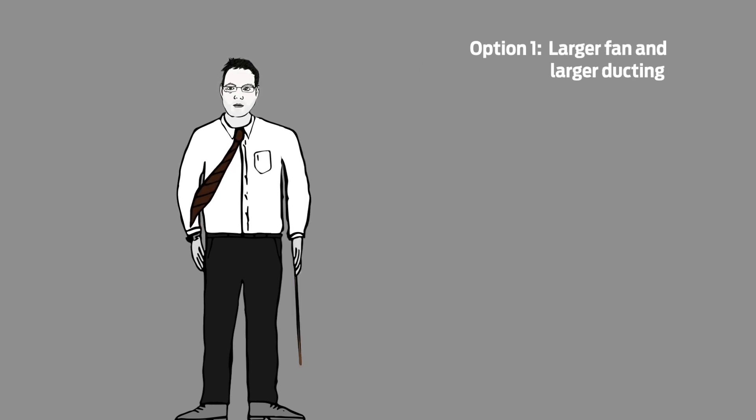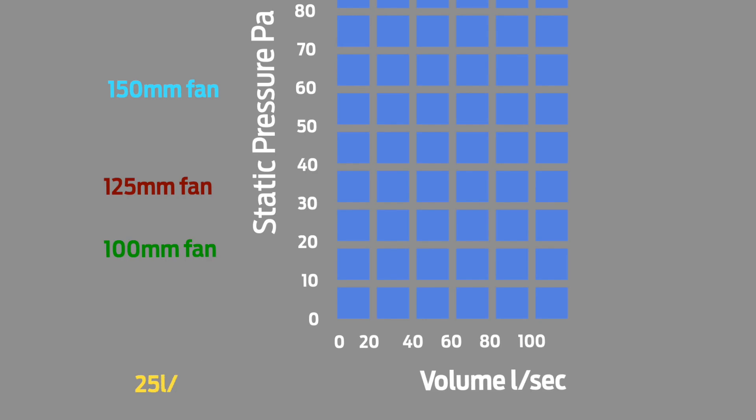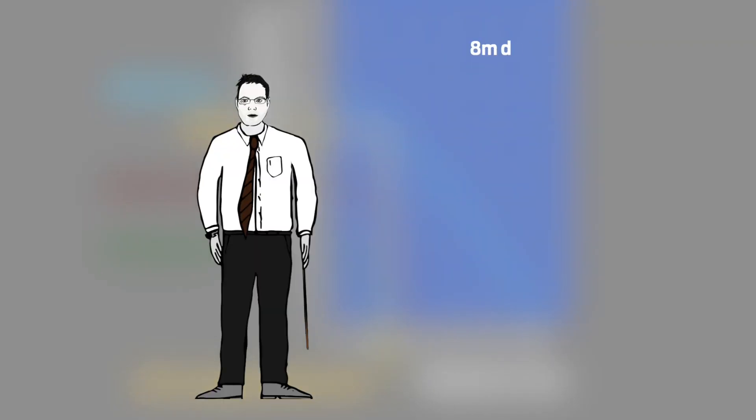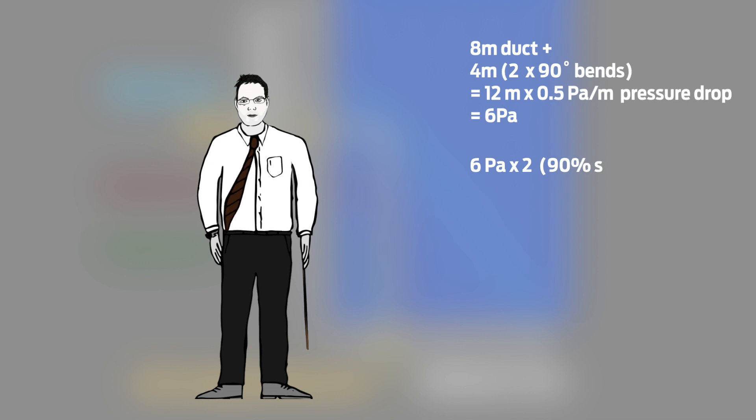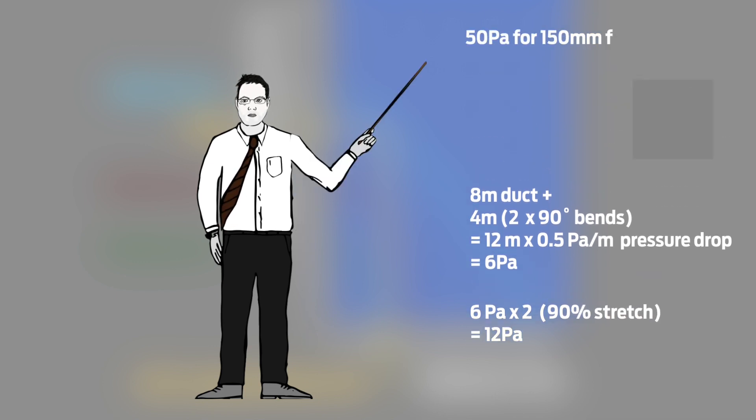Let's try the larger fan of 150 millimetres. At 25 litres per second, we can cope with around about a 50 Pa pressure drop. 8 metres of duct plus 4 metres for the bends gives us a pressure drop of 12 times 0.5, which is 6 Pa. If we double this for 90% stretch, it is only 12, so well within the 50 Pa the fan can overcome.